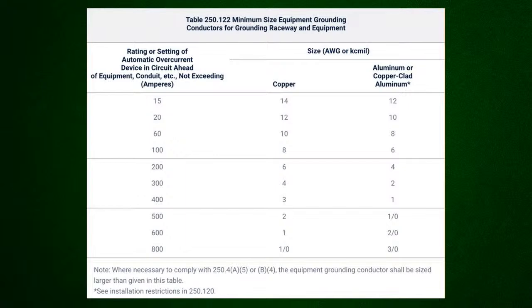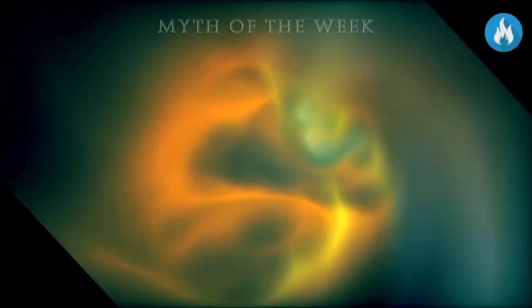You know, he's going in and at this point he's sort of making assumptions, because he has not gone back at this point and looked at 310.10(G), where it deals with the parallel conductors when you run them in parallel. And furthermore, let's just say I parallel for a multi-conductor cable, you're going to have to make sure that if you add any of those up together, that circular mill is going to have to exceed at least what? 1-aught, because you can't have smaller than a 1-aught in there, right? Yeah. Okay. So let him keep going.